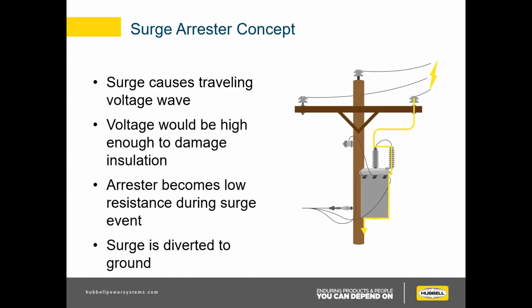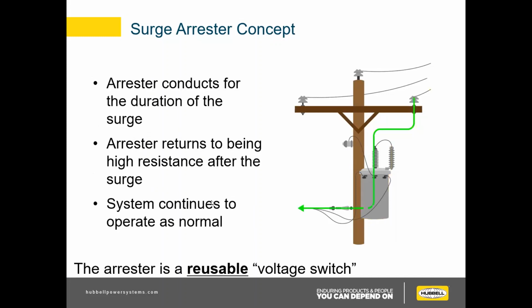When a surge comes, it causes a traveling wave like we just talked about, with a voltage high enough to damage insulation. The arrestor turns on to become a low resistance path to ground during the surge event, and the surge is diverted to ground. And the arrestor conducts the surge for the duration of the surge, and it returns to being high resistance after the surge. Like I said, this happens generally in milliseconds or even microseconds, and the system operates as normal. So the arrestor is a reusable voltage switch. These are definitely not a one and done device.